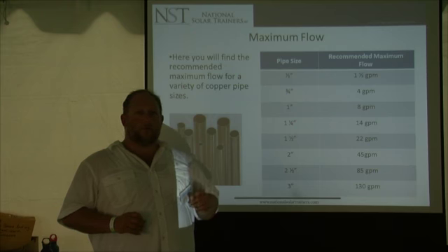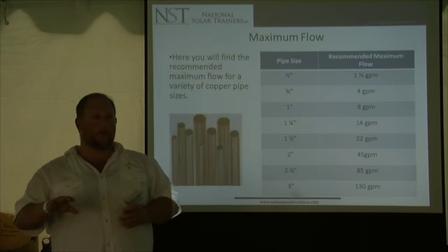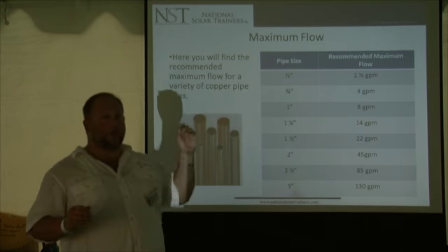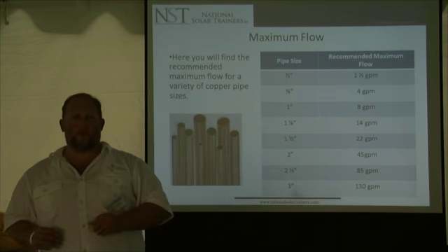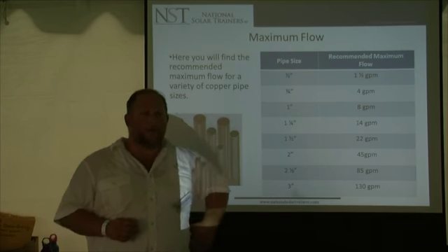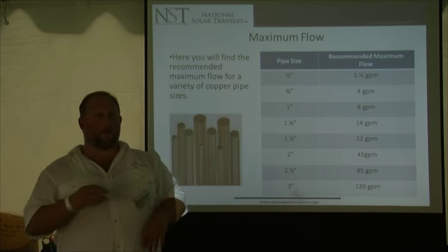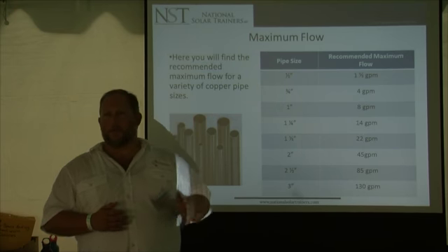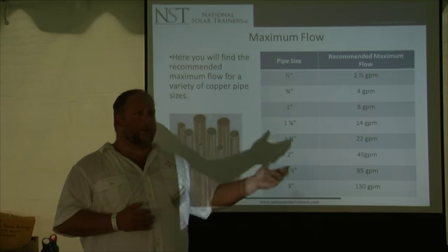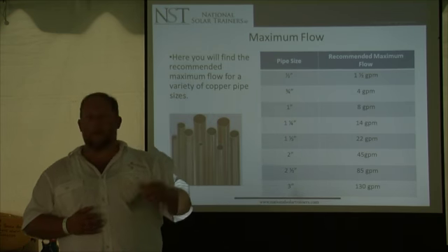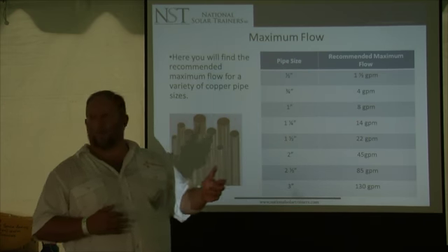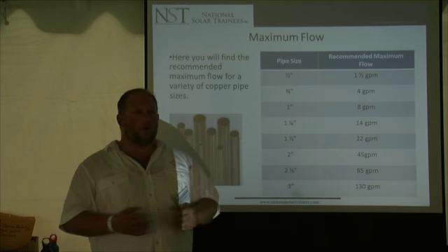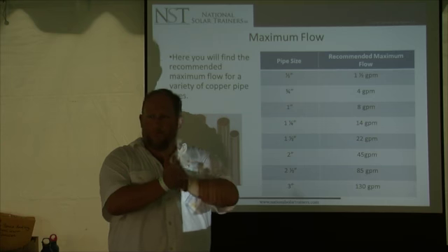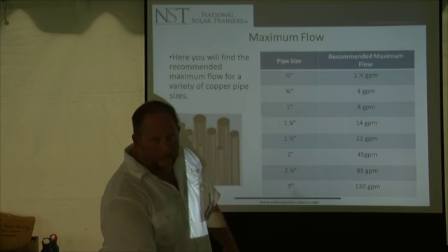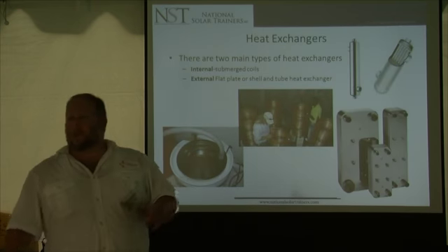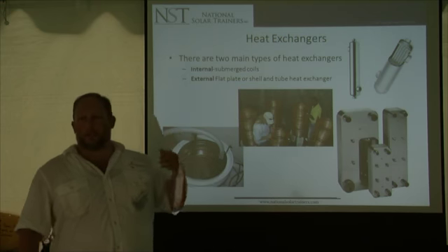Okay? And this is where, any plumbers? Plumbers generally will send 8 gallons a minute through a 3/4 inch pipe. That's what they're taught, and that's fine. That's cold water. Well, the hot water will increase the corrosion and erosion of the pipe. So it has to be down to about 3 feet per second. So now I can do about 3.5 gallons a minute through 3/4 inch pipe above 140 degrees. Otherwise, in about 5 years, the copper is going to erode away because of the abrasion of the minerals and the copper. The use of deionized water also, just to bring that up. I just ran into this issue yesterday.